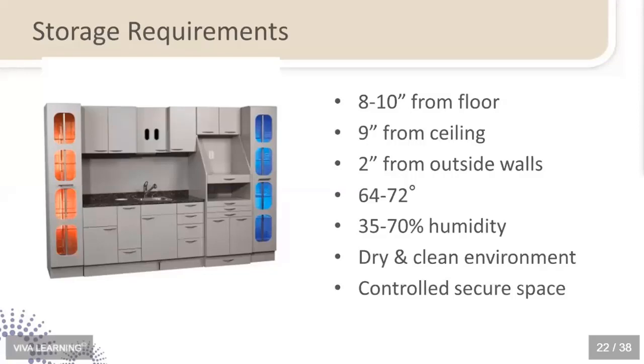You want to make sure it's a clean and dry environment in a controlled and secure space. You'll notice that the packaging area in this sterilization center has a demarcation - an actual physical wall between the cleaning and prep area and the clean, dry, controlled space for wrapping. You should have a demarcation between your cleaning prep area and your wrap area, even if it's something as simple as a piece of tape on the countertop. That is a CDC guideline.